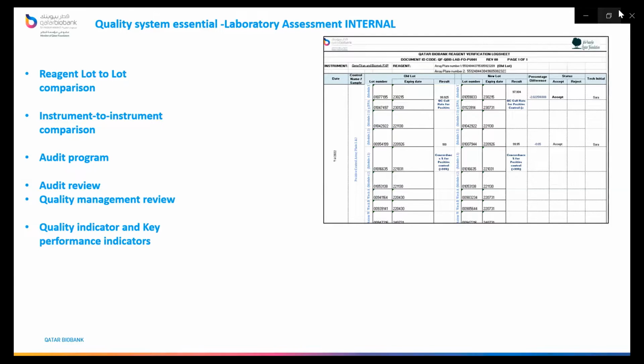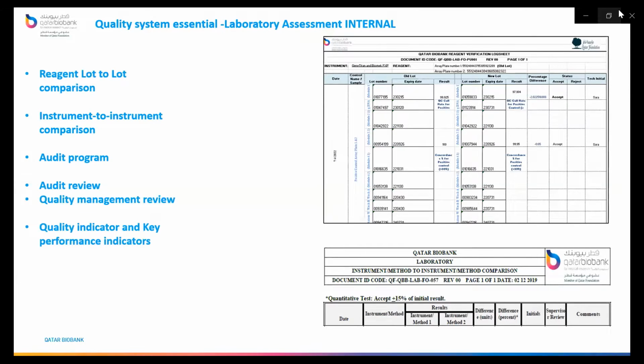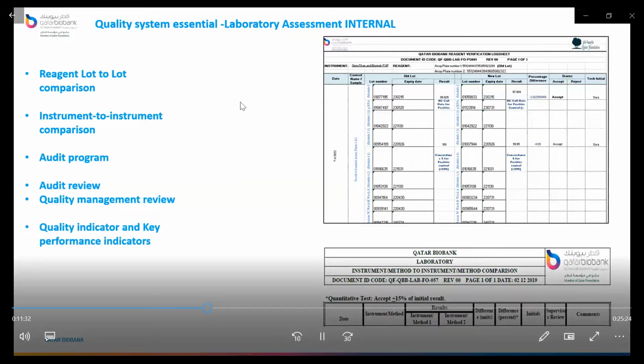We have set up the criteria by which we accept or reject the lot. At the same time, in most labs there is something called instrument-to-instrument comparison or method-to-method comparison. If we have, for example, automation and a manual process for, let's say, DNA quantification, we want to know that in case we have any downtime for the automation, we can easily perform a manual one, and this will not compromise our results. So we implemented periodic comparison with a set of acceptance criteria between two methods. And if we have the same instruments, we have to make sure that they are interchangeable at any time, because we don't know what can happen or what kind of workload we are going to get. So this is one of the measures that we implemented.